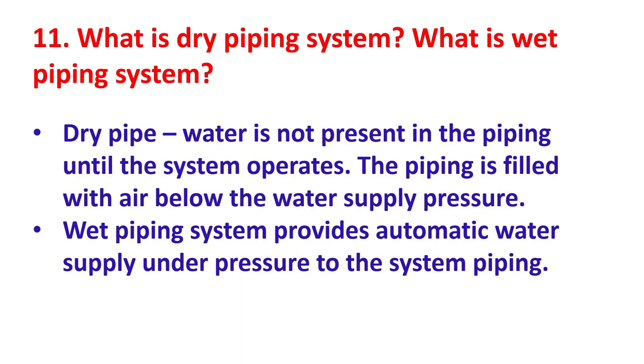What is a dry piping system and what is a wet piping system? In a dry pipe system, water is not present in the piping until the system operates; the piping is filled with air below the water supply pressure. A wet piping system provides automatic water supply under pressure to the system piping at all times.